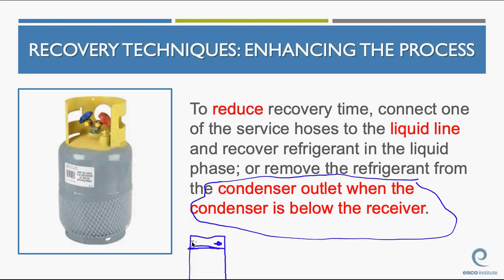Because of high wind conditions or some other reason, they didn't put the condenser on the roof. They put the condenser on the ground outside. Okay? My condenser may be down there, my compressor's up there, my receiver's up there. All I have down here is a remote condenser with a fan. My condenser is now down below the level of all of the rest of my system. So the liquid refrigerant, because of gravity, is going to want to sit down here at the condenser. Does that help?